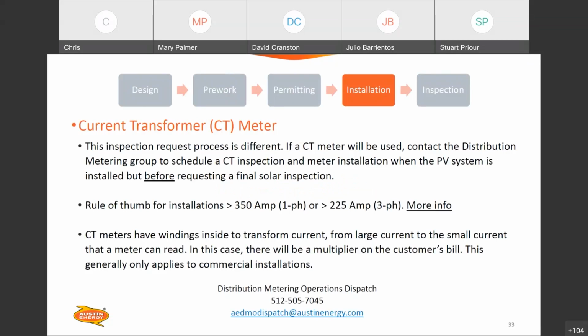So CT meter cans, these are different than the self-contained meter cans that we generally install in residential applications. If the service is large, generally in commercial situations, you will have a CT meter, which means that there will be a parallel inspection process, which will not involve one of the 3 of our solar inspectors. So you will need to have an inspection solely for that meter can. You'll need to have that meter set in place and the system commissionable before we can go out and do a true inspection on any of those projects that have that CT meter can.